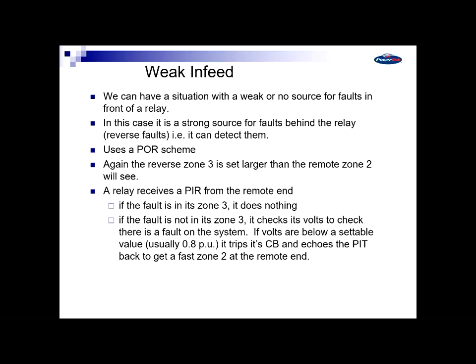If you're a weak in feed and there's a fault on the feeder between us, basically the way it works is I send a signal to you to tell you I can see a fault in front of us. If it's behind you, you say, yeah, I can see it too, but it's behind me, and you do nothing. If it's a zone 1, I'm already going to trip. If it's a zone 2, I do nothing as well. But if you can't see it behind you, you then go and look at your voltage. So you may be weak in feed, but your volts won't be healthy. So you'll see you haven't got healthy volts. You can't see a fault behind you.